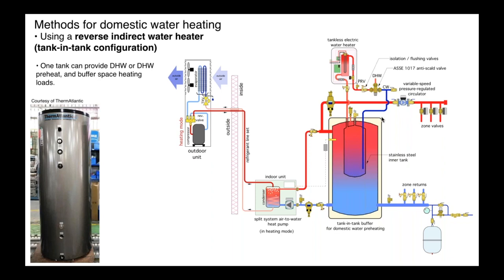And again, depending on the flow rate of domestic hot water, the dwell time in this tank, the temperature of the outer tank, you either are preheating or perhaps fully heating. So again, I'm showing it going out to a tankless electric water heater as a boost, okay? And then an anti-scald valve in here, especially if you're going up to 140, 150 for sterilization reasons, you don't want to send that temperature off to the fixtures. So you can see there's quite a few different options here for incorporating domestic water heating into the system.